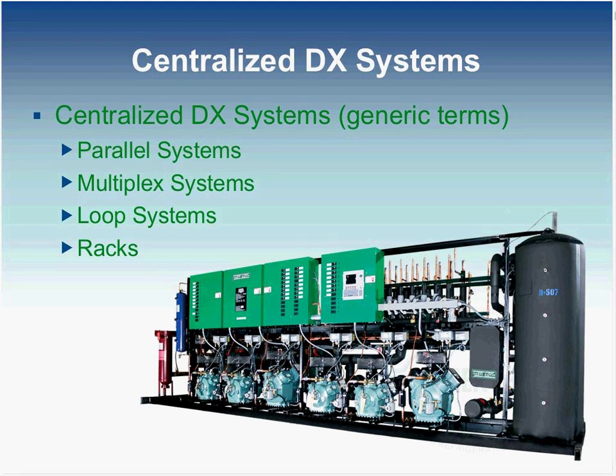In the slide here, it shows a typical rack. And on a rack, you take a number of compressors, mount them onto some steel support structure, and ship the unit complete to a store. A grocery store may have it installed in the back room, or it may be put on a mezzanine in the back of the store, possibly set on the roof, or possibly enclosed in a house and set on a concrete pad out behind it.